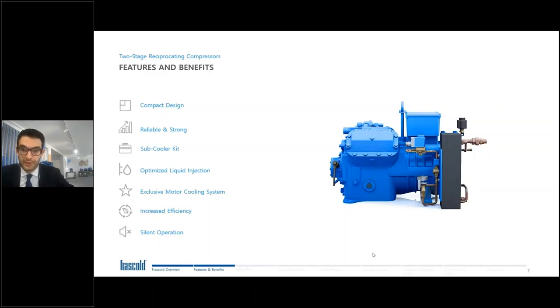Here is how the compressor looks. Without the external pipes, the compressor itself becomes very, very compact. What you can see on the right is just the economizer, an option that can be there or not, a subcooler kit or economizer. The compressor itself is very reliable and strong. The liquid injection is optimized, and we will see how, with the exclusive motor cooling system. The total efficiency of the machine is increased, and the operation is really silent.